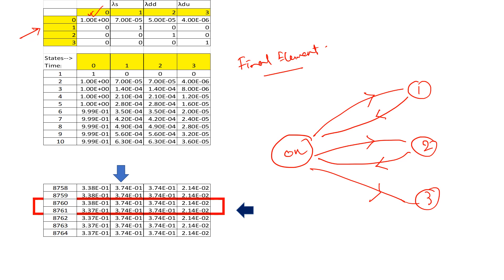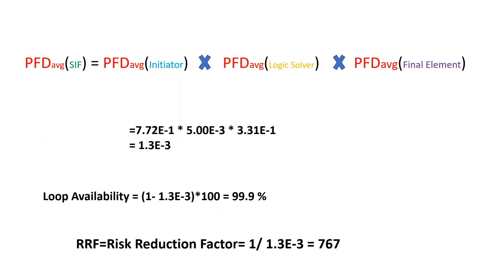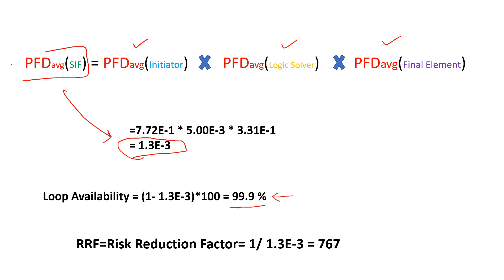We have calculated the PFD average for the final element, initiator, and logic solver. Since all three components are in series, the total SIF PFD average is the product of their individual PFD averages. The availability of the loop is 1 minus PFD average, expressed as a percentage — which comes out to 99.9%. The risk reduction factor (RRF) is 1 divided by PFD average, giving a value of 767.